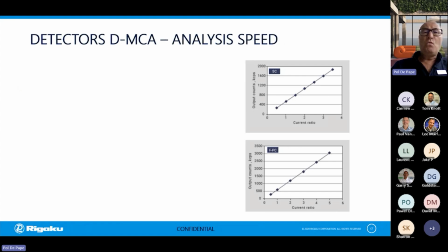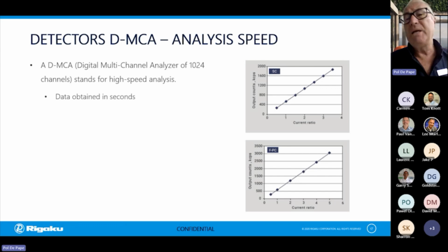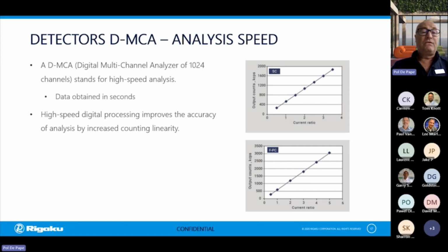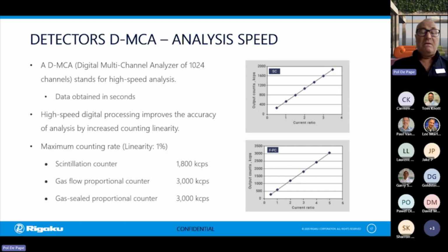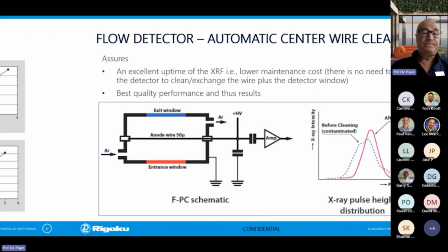So analysis speed is really one thing that is important. We have now built-in digital multi-channel analyzers, which contain 1024 channels. So this really stands for high-speed analysis. This means we measure all the incoming photons at the same time. So data is really obtained in a few seconds. And this, of course, improves the accuracy of the analysis because we have an increased counting linearity. So for our scintillation detector, we have a linearity of up to 1800 kcps. And for the flow proportional and the gas seal detector, we have a linearity of up to 3000 kcps. This means we can catch really many photons.